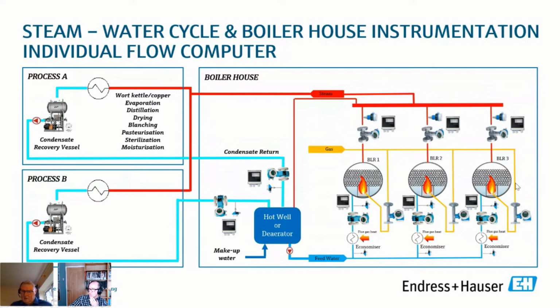Next to each of these meters is a little flow computer, calculating the mass and the heat. Most of these meters, like the steam meter here, measure the volume, so there's a pressure transmitter or a temperature sensor plus a flow computer. That's how we measure the mass and the heat.